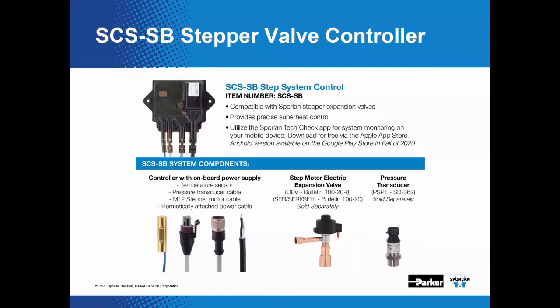As seen on this slide, when you apply this controller in a retrofit application, it's going to be very simple because, again, all of those valve cables that in the past you had to buy separately are all attached to the controller. To simplify the install, it also supports a variety of transducers, all of Sporlan transducers, and even some external valves that you may not get from Sporlan. You can also set this controller up to support those transducers and those valves. So it's a very good, easy to use, easy to install controller.